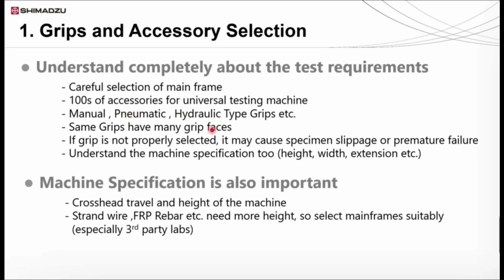Even the same grip can have different grip face options. For example, sometimes polymer or thin film type samples may need rubber coated grip faces. Some other samples like geotextile might need wave type grip faces. So all accessories should be carefully selected. If the grip is not properly selected, it may cause specimen slippage or premature failure. Non-uniform samples may need special grip faces.